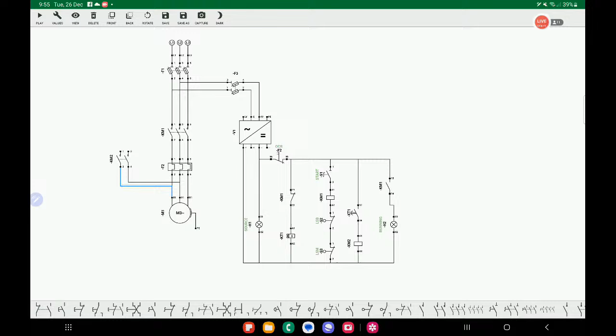this contact, and now I will put another fuse that will separate our space heater into our system. Now I will connect it to these windings, to these lines. Okay. So right now, if I play supply, I'm not doing anything onto the S1. Now I have a winding supply of the heater onto the windings of our electrical motor. So it means if there is an inactivity onto our system, this only means that the space heater, the winding heater, is working. Okay, so this is a simple setup that you might use, no?